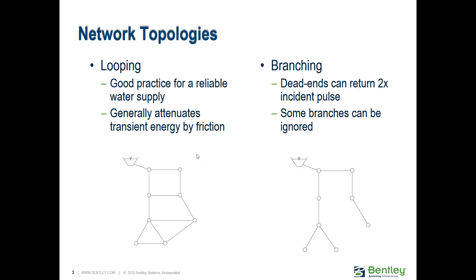There are two main types of network topologies: looped systems and branched systems. Looping generally attenuates transient energy more since waves have different paths to travel and tend to dampen out better. In branched systems, when a wave hits a dead end it can return with the opposite sign — basically two times the incident pulse.